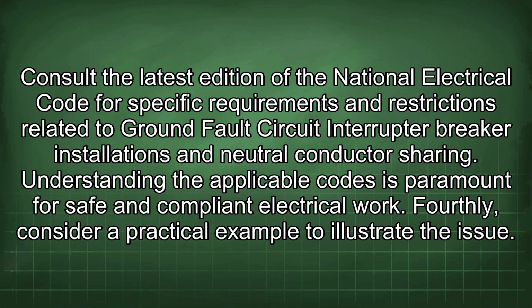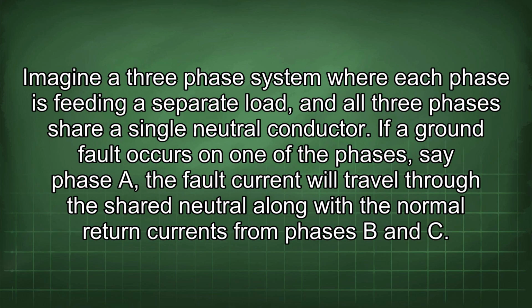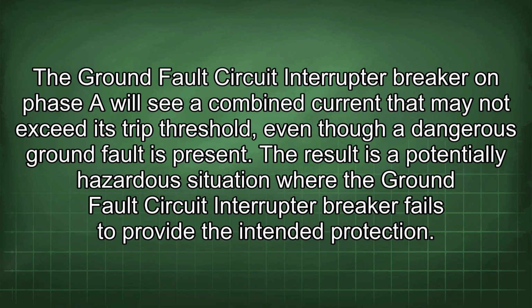Fourthly, consider a practical example to illustrate the issue. Imagine a three-phase system where each phase is feeding a separate load, and all three phases share a single neutral conductor. If a ground fault occurs on one of the phases, say phase A, the fault current will travel through the shared neutral along with the normal return currents from phases B and C. The ground fault circuit interrupter breaker on phase A will see a combined current that may not exceed its trip threshold, even though a dangerous ground fault is present. The result is a potentially hazardous situation where the ground fault circuit interrupter breaker fails to provide the intended protection.